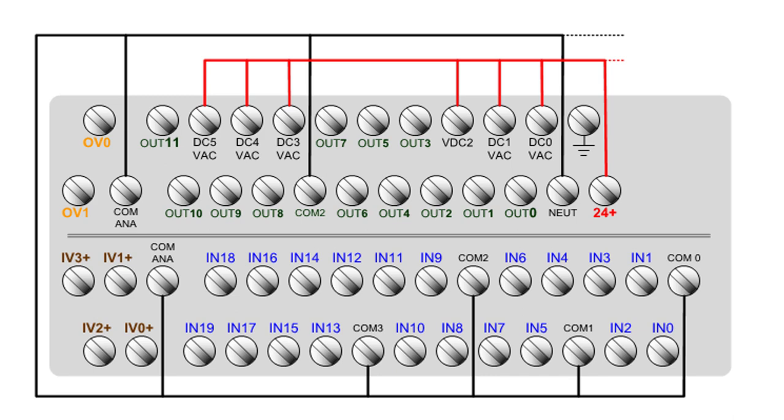So now you see I've connected all the 24 volt DCs together. DC 0, DC 1, 3, 4, and 5. The reason I do that, even though I'm not going to use necessarily anything above output 5, which gives me 6 outputs wired up to 6 LEDs, is that everything's all wired up in advance, so in the field, if I need to connect up something in a hurry, everything's already jumpered together. All I have to do is add additional I/O wiring.